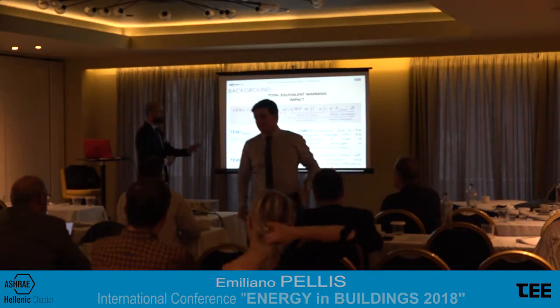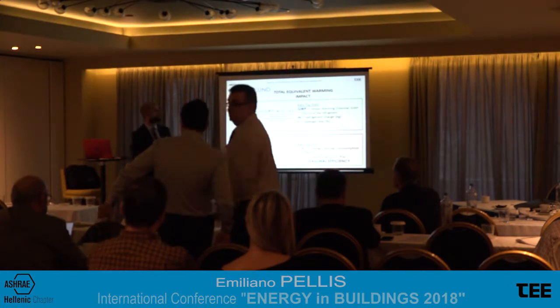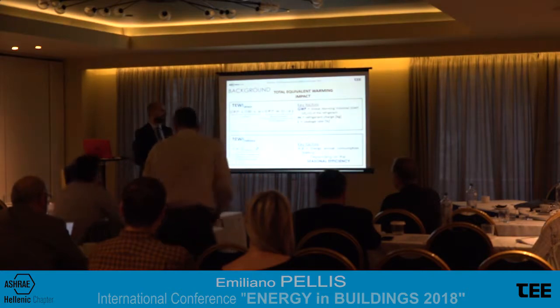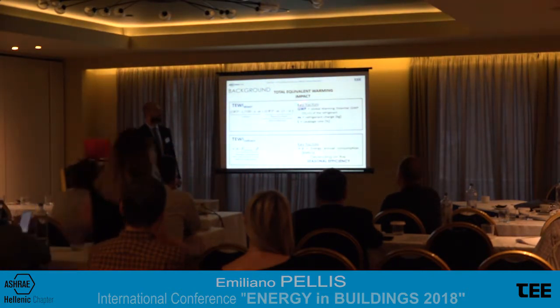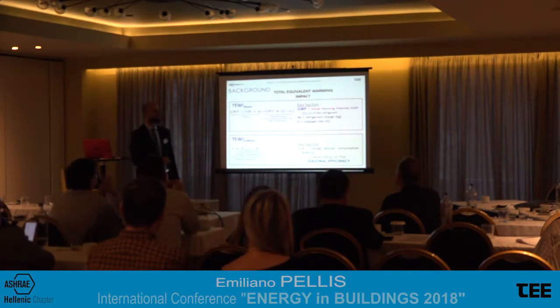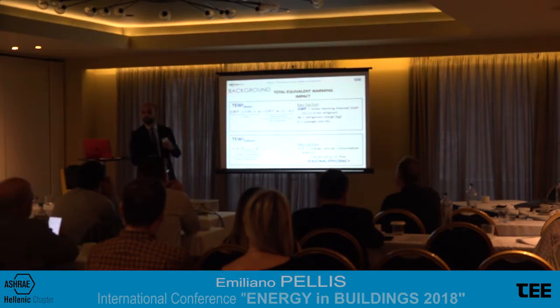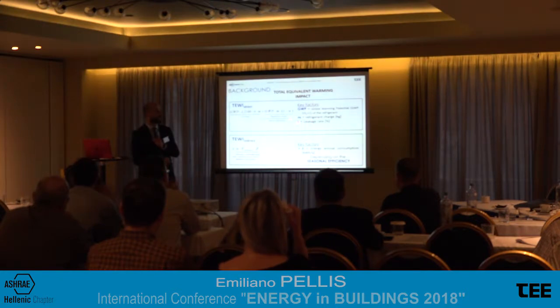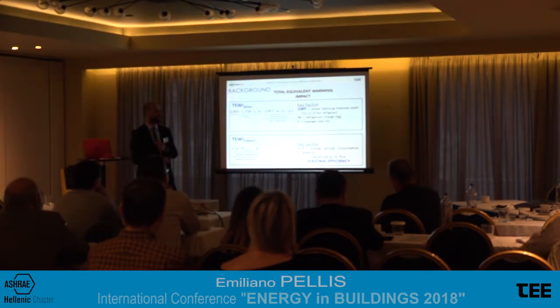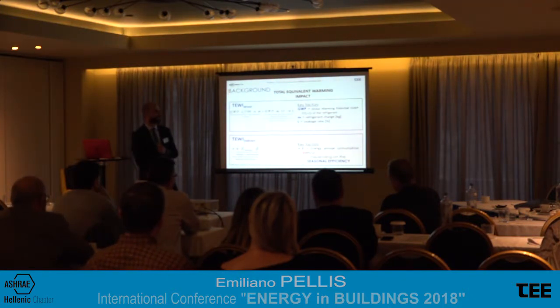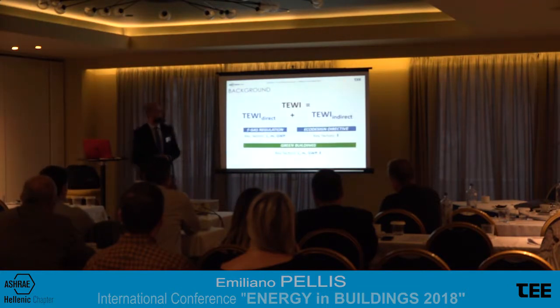So, total equivalent warming impact, direct and indirect. If we explore in detail the formula for the TEWI direct, we see that it depends mainly on three key factors. GWP is the global warming potential of the specific refrigerant compared to CO2, which has a GWP conventionally equal to 1. Then there is M, the refrigerant charge, so basically the refrigerant content in kilograms for the chiller. And then L is the leakage rate. If we move to the TEWI indirect and again explore the formula, we see that it depends mainly on the factor E, the annual energy consumption, so basically depending on the seasonal efficiency of the unit. So we need to reduce the total TEWI, the direct plus the indirect.